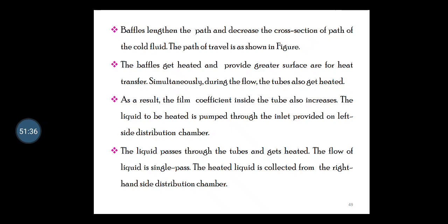So the baffles get heated and provide a greater surface area for the heat transfer. Simultaneously, during the flow, the tubes also get heated. As a result, the film coefficient inside the tube also increases, and the liquid to be heated is pumped through the inlet provided on the left side distribution chamber. The liquid passes through the tubes and gets heated. The flow of liquid is single pass, and the heated liquid is collected from the right hand side distribution chamber.